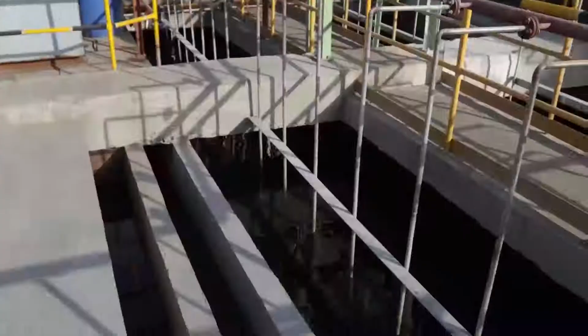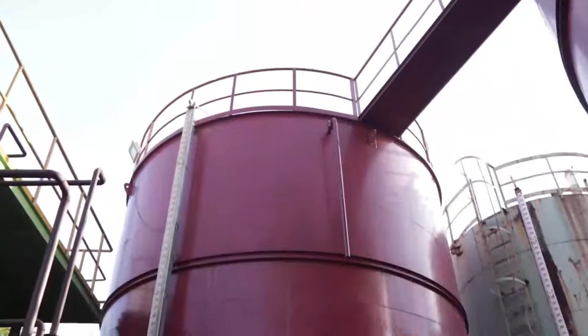The fire pump house is very well equipped with 3 separate firefighting systems. Each system consists of a jockey pump, electrical pump, and a diesel engine pump. The facility has a water storage tank with a capacity of 750,000 liters for the use of firefighting.